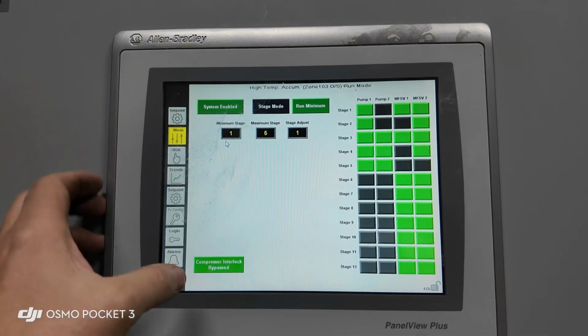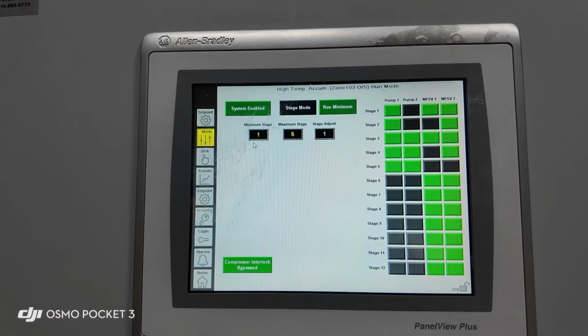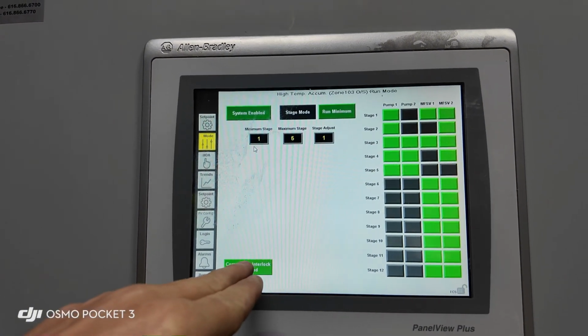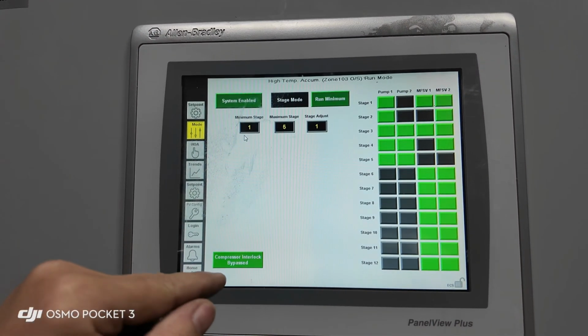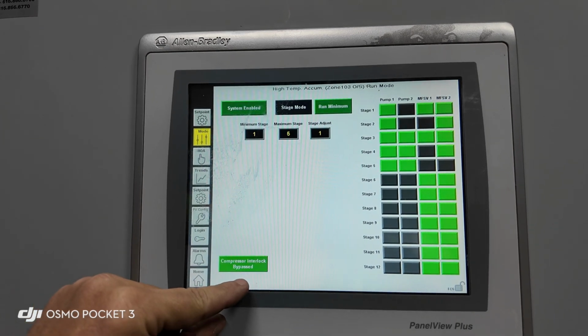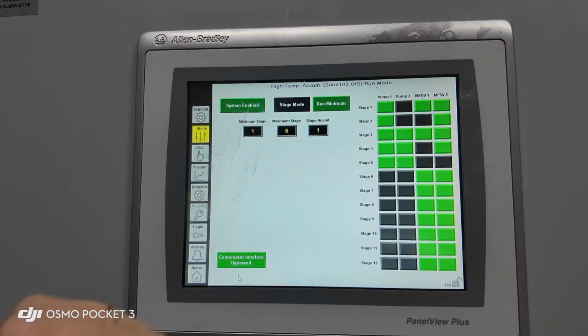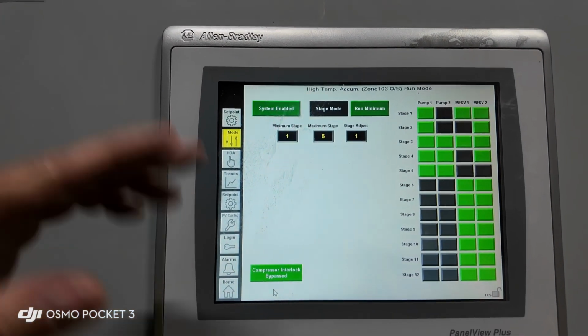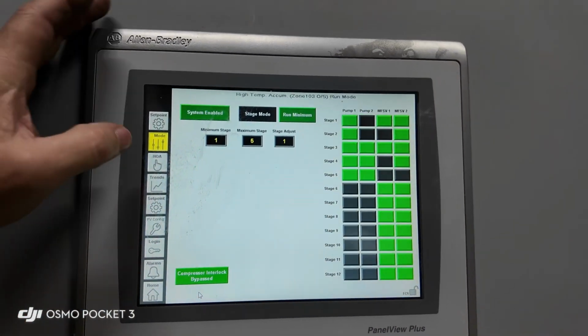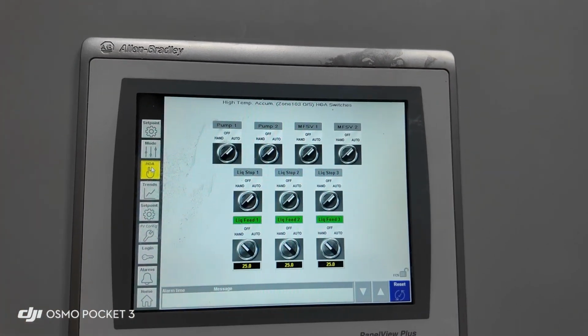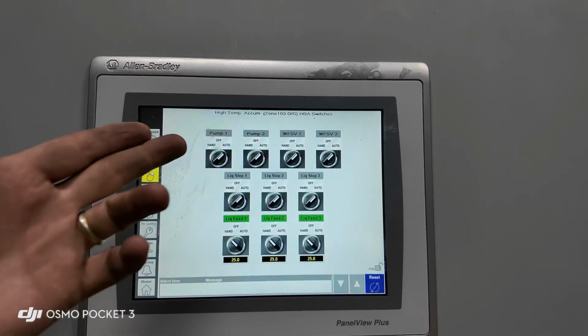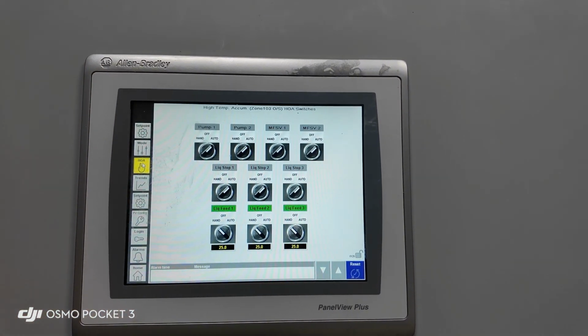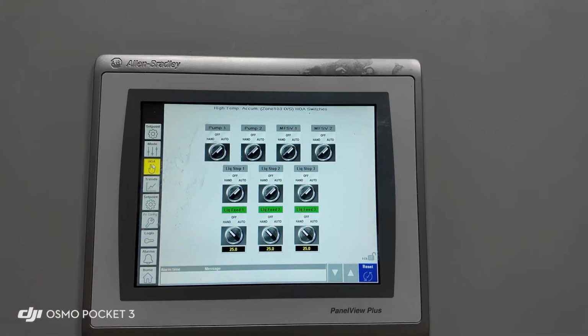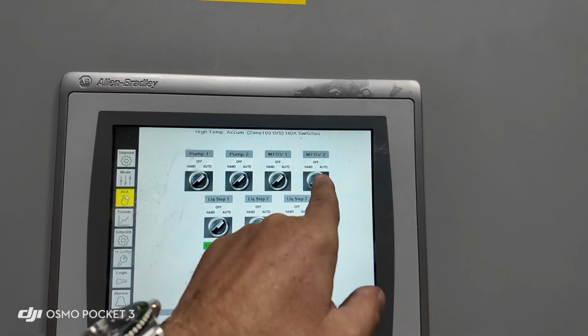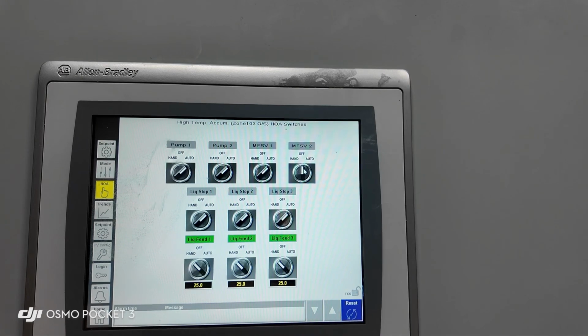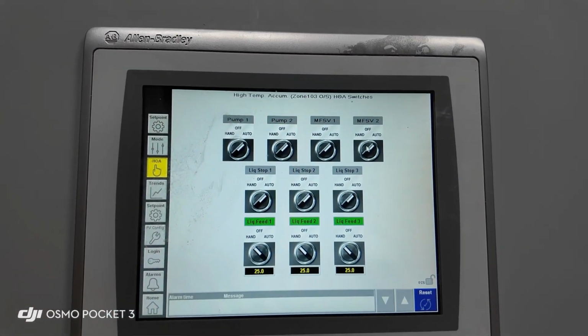Okay? There's a compressor interlock bypass button here. By pressing that button, it will not allow the system to run if no compressors are running. While I have them bypassed, it will allow the system to run whether it can detect a compressor running or not. These are logical HOA switches. There's one for pump 1, one for pump 2, one for pump minimum flow solenoid valve 1, minimum flow solenoid valve 2. To change them, I touch them, and they will change position.